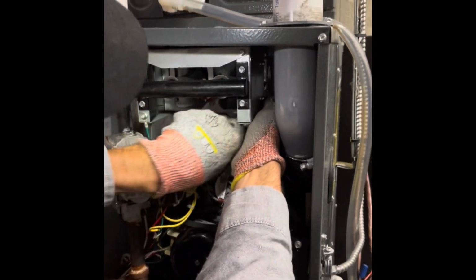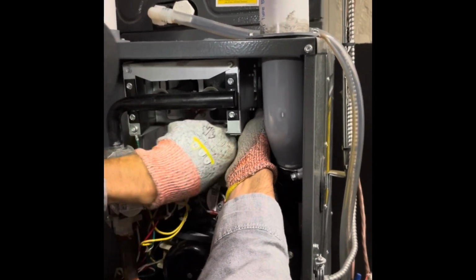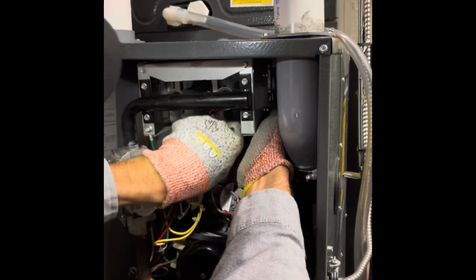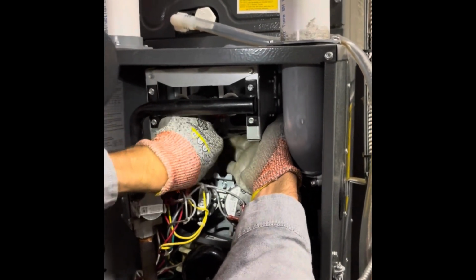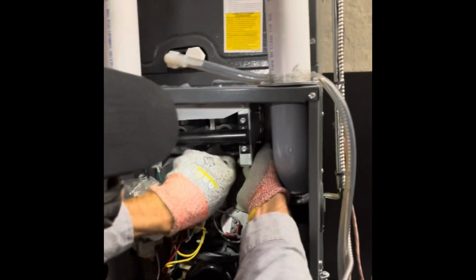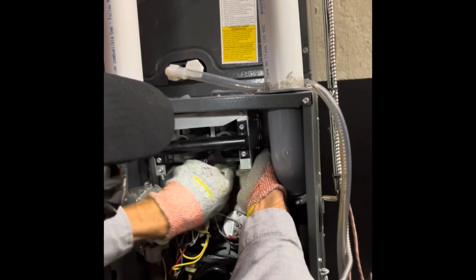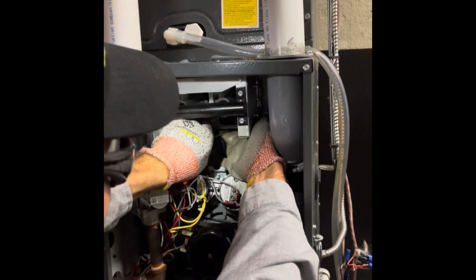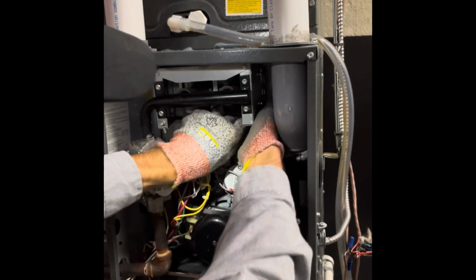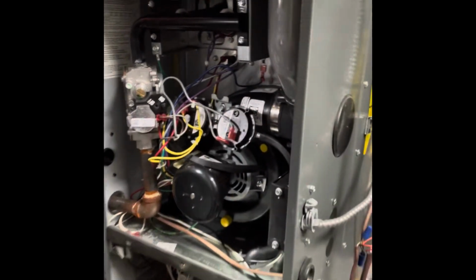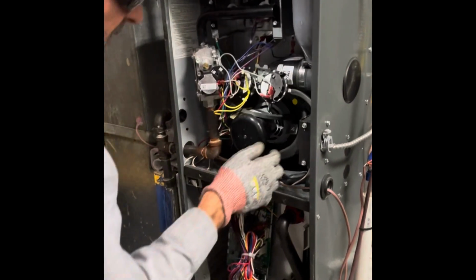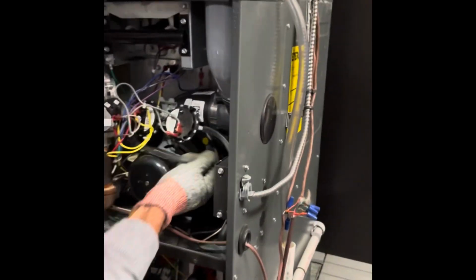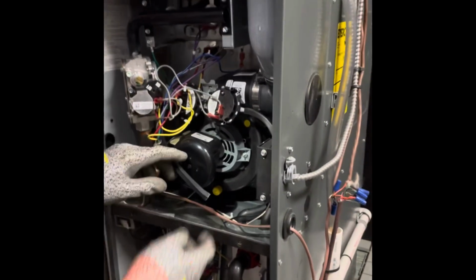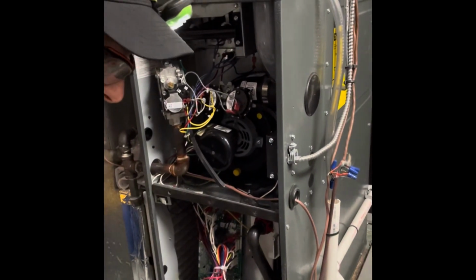So when I get this done, I'm going to continue on with those condensate hoses. I want to clear all the hoses out of any moisture or debris that could be in there. It just takes a bit of moisture in these hoses to prevent the switch from closing. In turn, we will see the furnace fail in operating mode. So first things first, I'm going to remove this tube here.